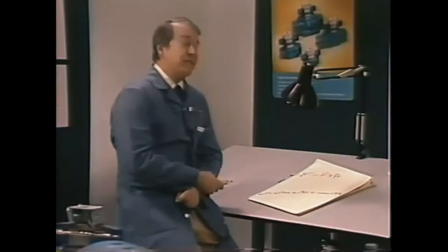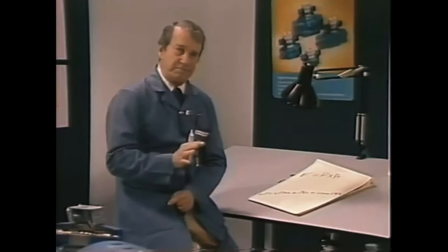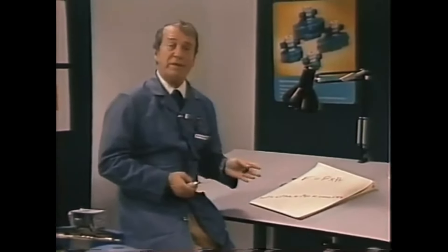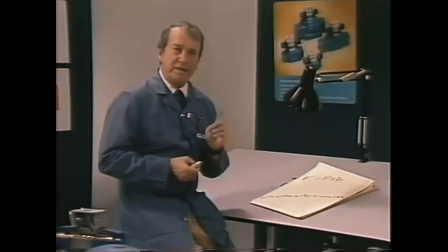Actually, this formula tells us the horsepower output of the pump. If the pump were 100 percent efficient, it would also be the input horsepower required to drive it. Unfortunately, pumps aren't 100 percent efficient. In fact, few things are. We would probably be safe in assuming that a well-designed pump in good condition should be between 80 percent and 90 percent efficient.